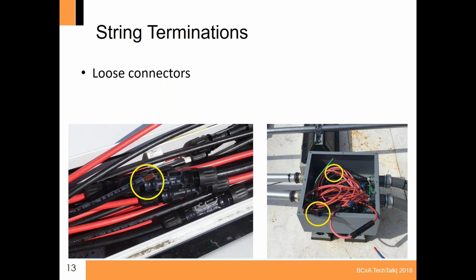It's not something that, while the system's running, we want to go pull on these connectors, but during the installation, this is basically where we verify that they're using the proper tool and the proper connectors. These connectors, the brands of the male and female match up. There are several different brands out there, and some brands don't play nicely with others, like anything really. But again, before the system is started up, we want to verify that these connections are made properly. After the system's up and running, it's extremely difficult, if not impossible, to verify this. It could also be dangerous if we start pulling on connectors where electricity is flowing through. It's like disconnecting a fire hose while water's flowing through. It's not a good idea.